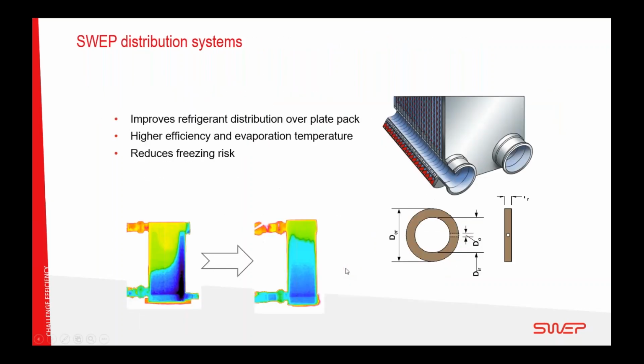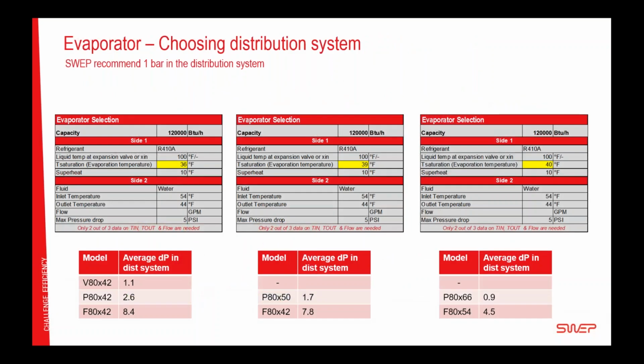So if we go back to the selection here, which is the best evaporator here, you have to decide. Can you accept only a little bit, with 1 bar? Then go for the V80. Can you accept the 2.6 bar? I would recommend the P80, because you will have a better evaporator in this case. And I don't think you can accept the 8.4 bar here, because 8.4 bar would be more than 30% of the total pressure difference in a R410A system typically.